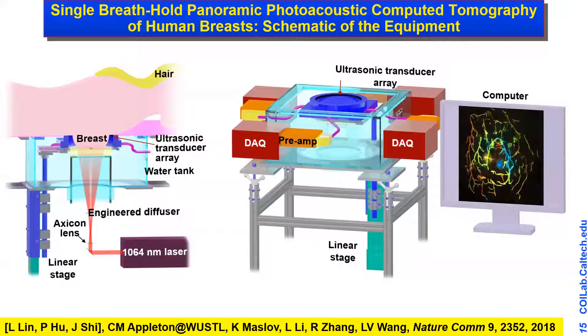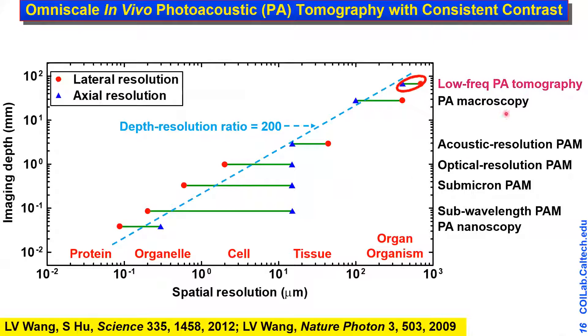We scaled up the system for human breast imaging. The aperture is 22 centimeters in diameter to accommodate most breasts. The breast is slightly deformed to stabilize it and minimize the penetration requirement for light. The system operates at multiple centimeters penetration with hundreds of microns resolution, enabling omniscale imaging — from whole human organs or entire small animals down to tissue, cell, and organelle levels.